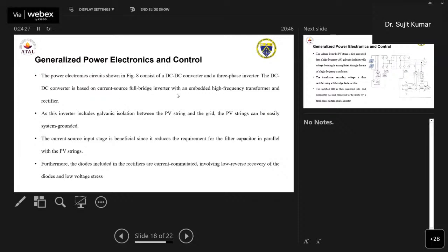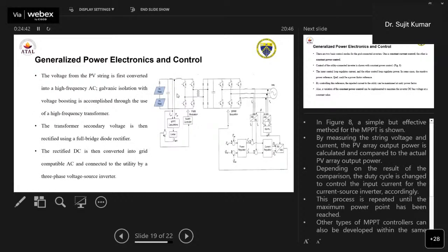So this part we have removed for the current source. As a further benefit, filter capacitors are not required. Furthermore, the diodes included in the rectifiers are current commutated, involving low reverse recovery of the diodes and low voltage stress. In this particular figure 8, the effective methodology of MPPT is shown. The voltage from the PV string is first converted into high frequency AC. Then galvanic isolation with voltage boosting is accomplished through the use of high frequency transformers. These are the high frequency transformers.